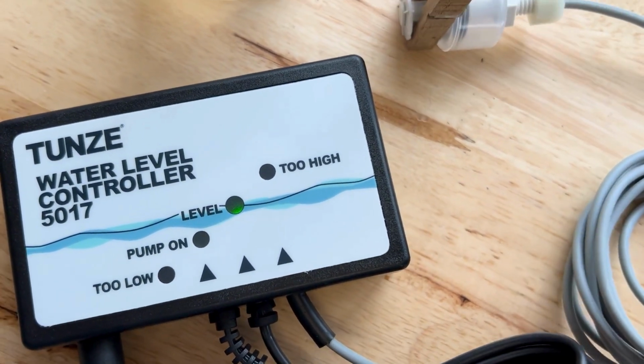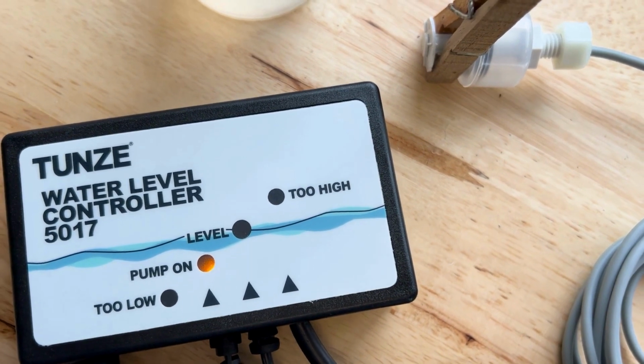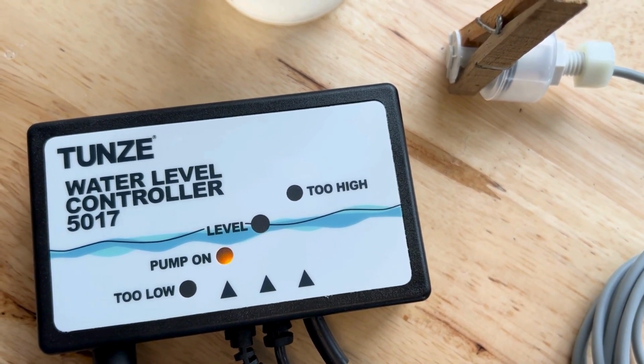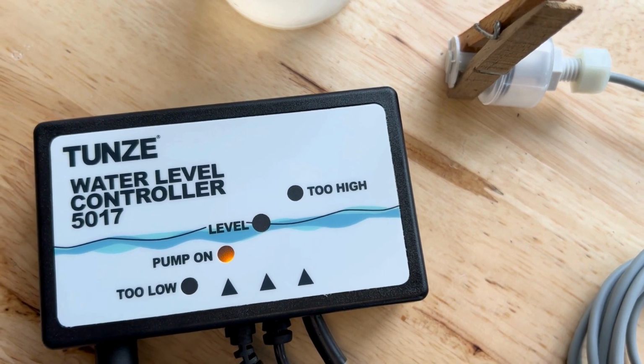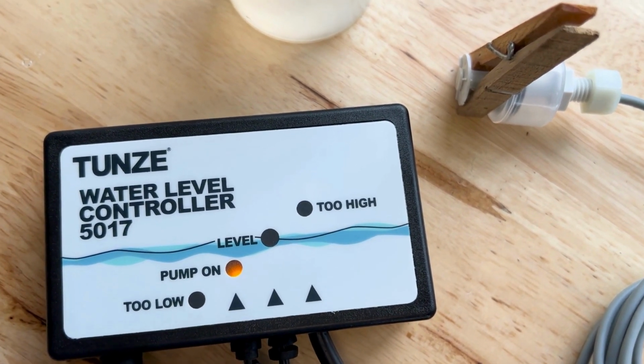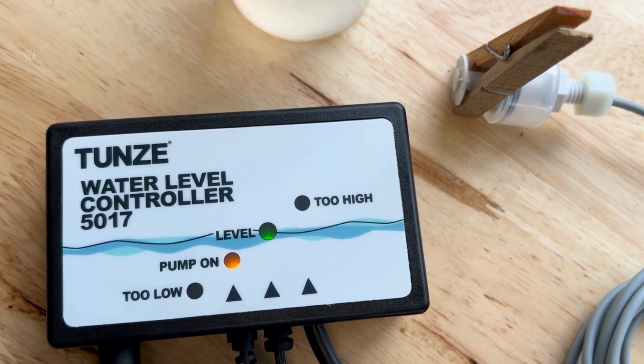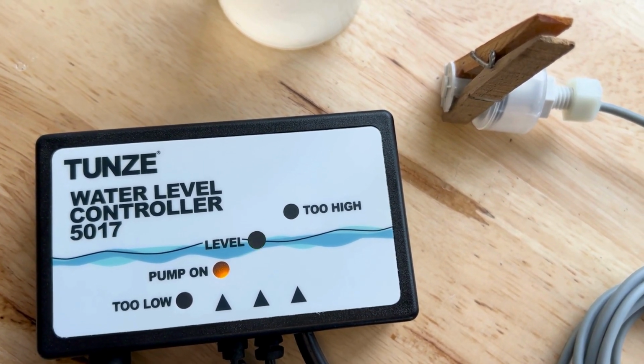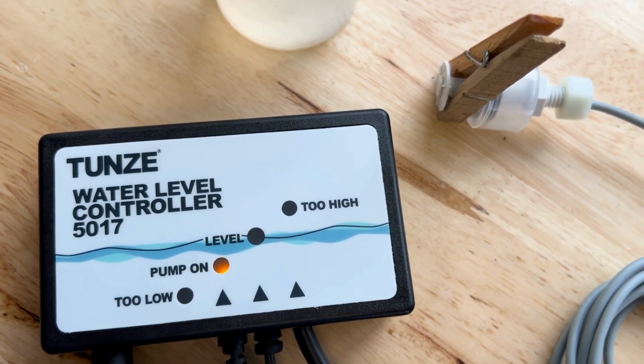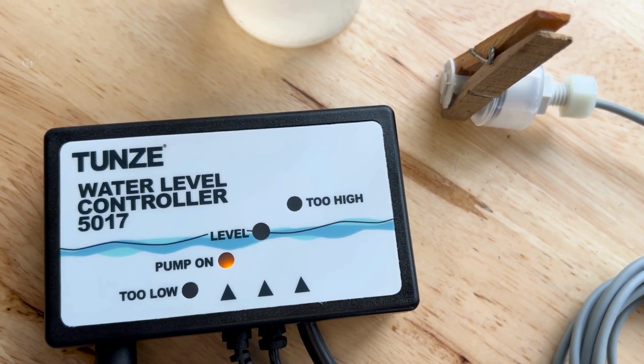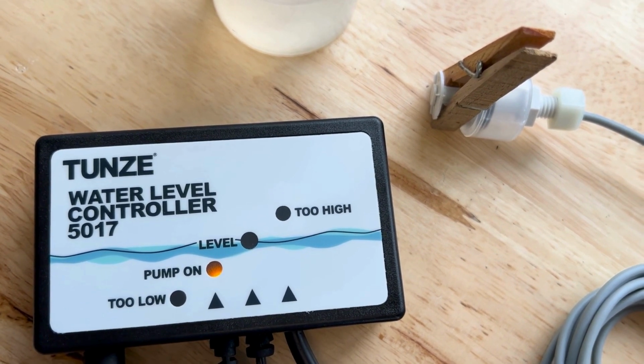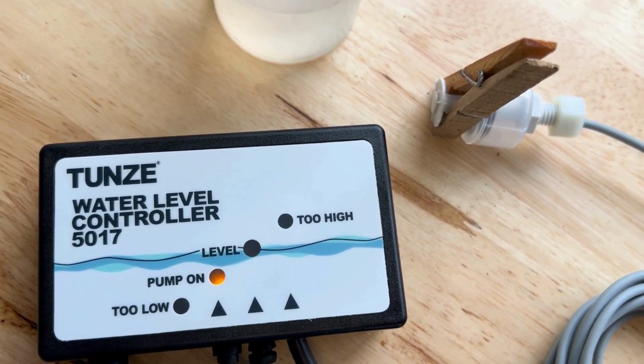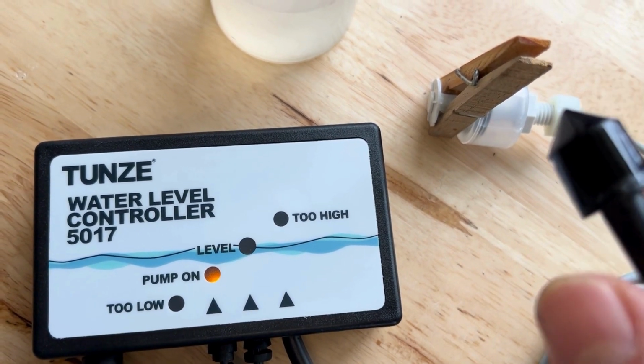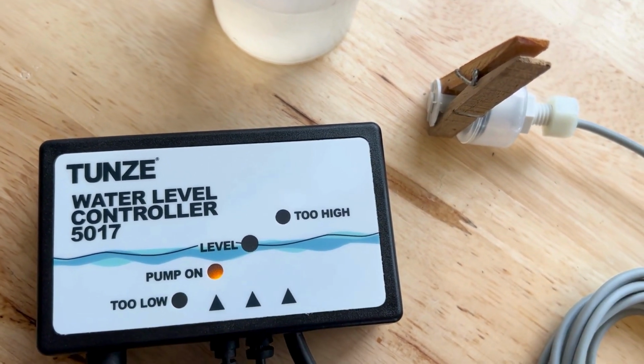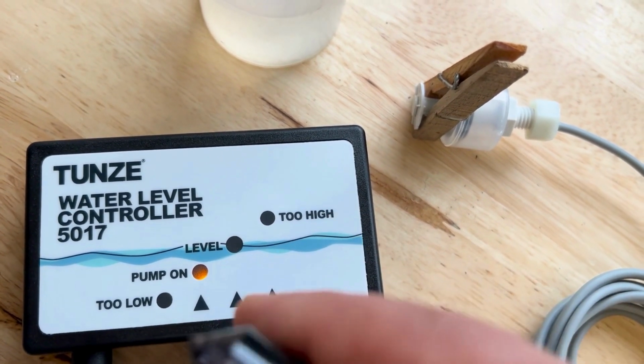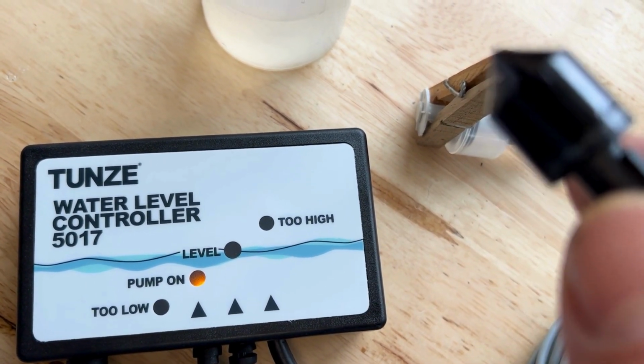Okay, we have our green level light. That means our optic sensor passed. Now it's going to run the pump. I should point out that when you start it up, it's doing a series of self-checks. One of those is to test the sensor. When you first power it up, you will get the green level light if the optic sensor is clean and dry. You will get a red fail light, the too low light, if the optic sensor is dirty or in water. And you can use this to diagnose your optic sensor, but you have to reinitialize every time you run the test because that test light's only on briefly at startup.